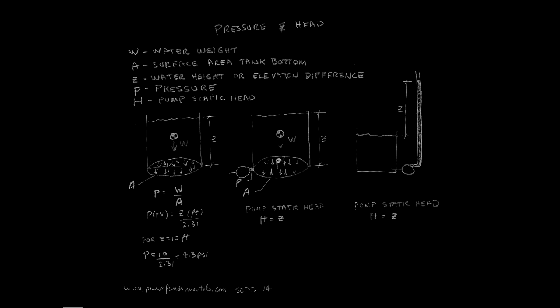Back to the filter. If the filter manufacturer says the filter will have a pressure drop of 3 psi at our flow rate, then we convert this pressure to head: 3 times 2.31 gives us 7 feet of pressure head drop. We add this amount to the head of the pump to make sure it has sufficient capacity to supply the filter.